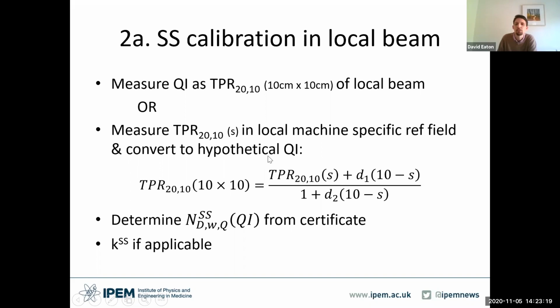So you can measure in a local field given some limits, but that would certainly include a 5 by 10 or even a 5 by 40 field for tomotherapy, a 6 centimeter circle for CyberKnife. We don't directly address Gamma Knife in this report. That is a more specialized condition, but the formalism for this report should certainly be compatible with some additional data for Gamma Knife in the future, and there is work ongoing to address that particular machine, which has a maximum collimator size of 1.6 centimeters, so quite a bit smaller. So once you have your TPR 20/10 for your 10 by 10 field, you can then determine your calibration coefficient from your certificate, and you can apply a k_SS value if applicable.